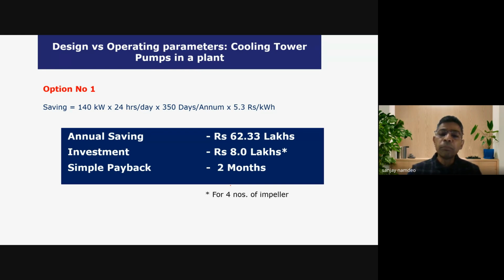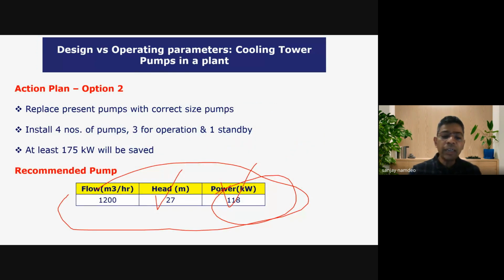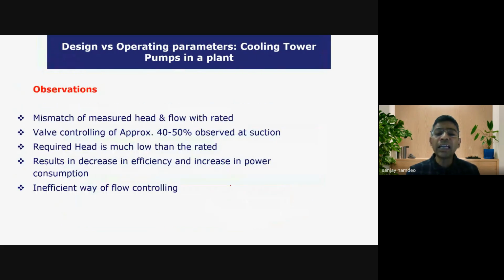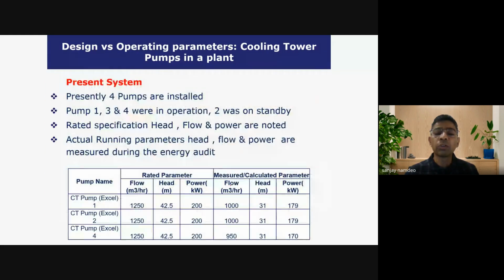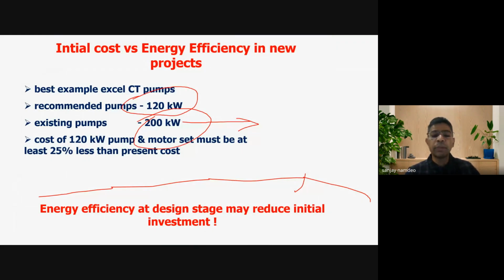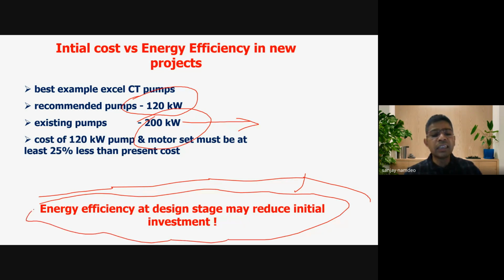So if this 120 kilowatt, 1200 meter cube, 27 meter pump, even if we take the best efficiency with a higher cost, still its cost would be less than the incorrect size pump of 200 kilowatt, 1250 meter cube and 42 meter head. So the message is, if we can design or size our equipment correctly, the initial investment would be less. So energy efficiency at design stage may definitely reduce the initial investment as well, right?